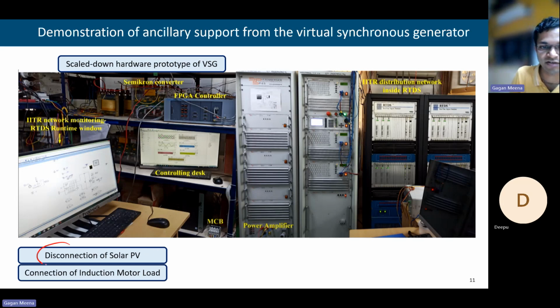One was disconnection of solar PV. If solar PV is disconnected, the load is more and generation is less, so there will be a drop in frequency. In that case, the virtual synchronous generator has to pick up and provide more power and bring the frequency back to its nominal value.